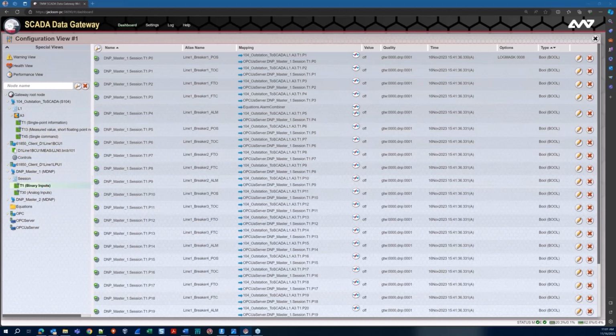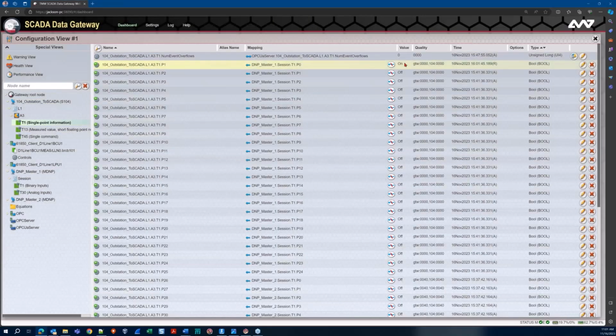Let's just change the first point in my DNP master 1, from off to on. So when I do that, we're going to see that value be passed through - the value change from off to on up here in my gateway. That, of course, will be passed up to the 104 side where I can see it reflected here, the values being sent.